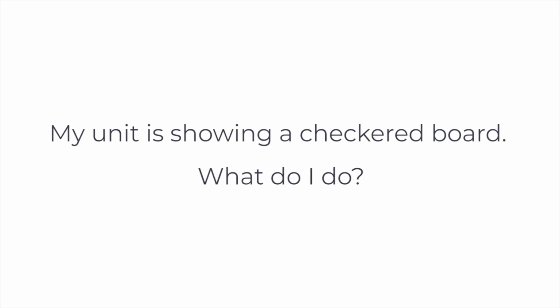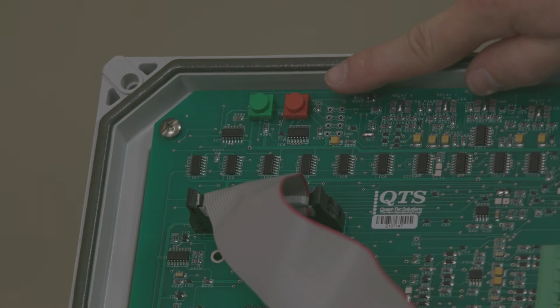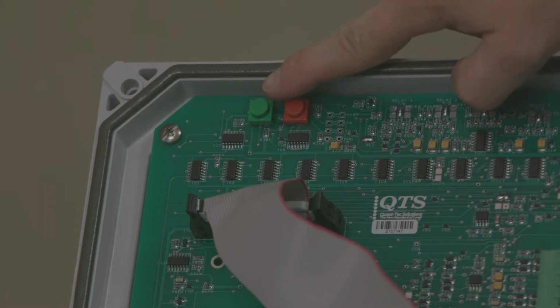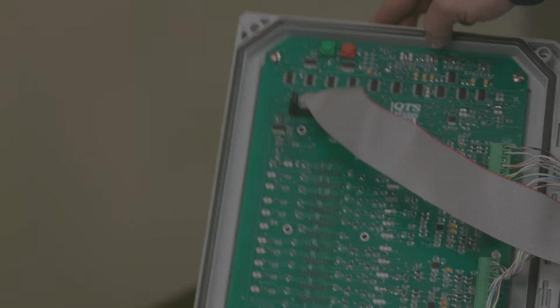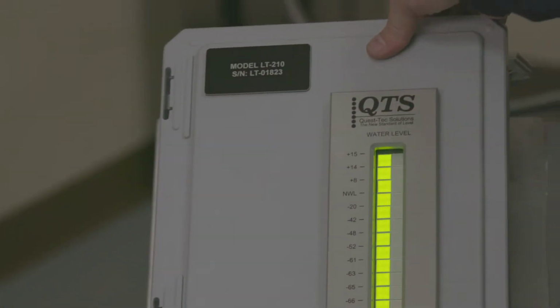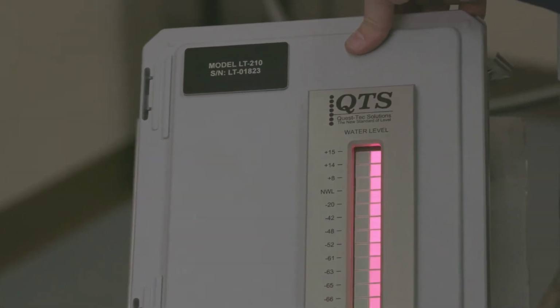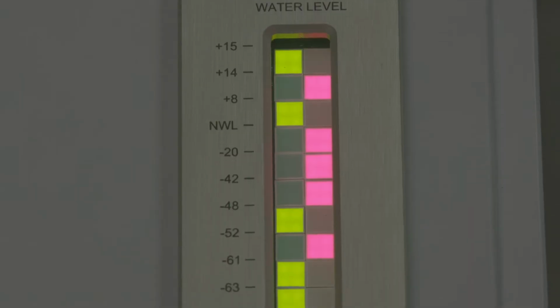My unit is showing a checkered board. What do I do? Press the test buttons. This condition can be simulated by unplugging one of the probe plugs. If the test buttons perform as intended, it is wiring. If the test buttons do not work, replace the discriminator PCB.